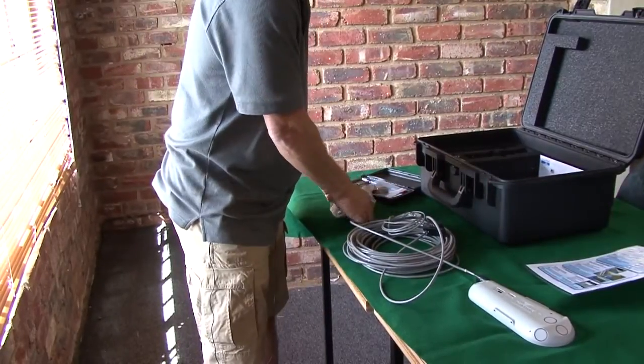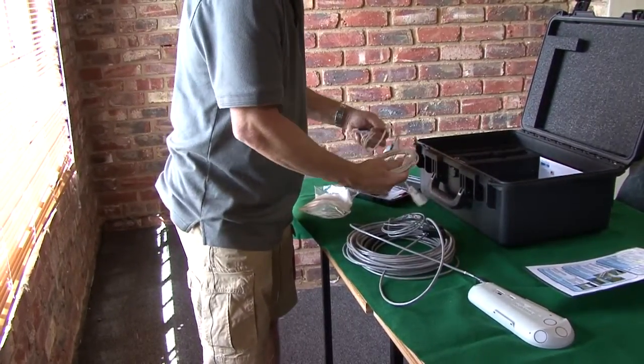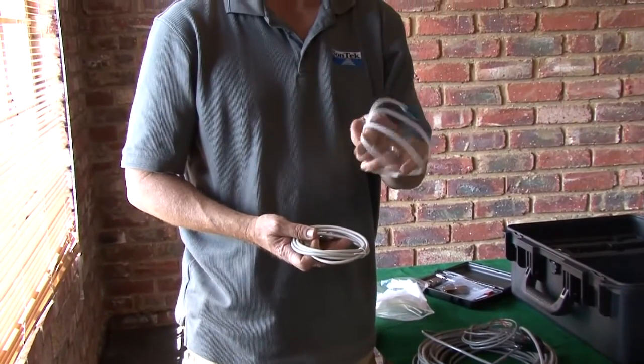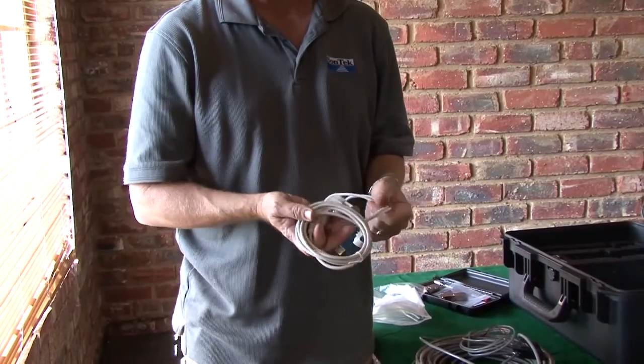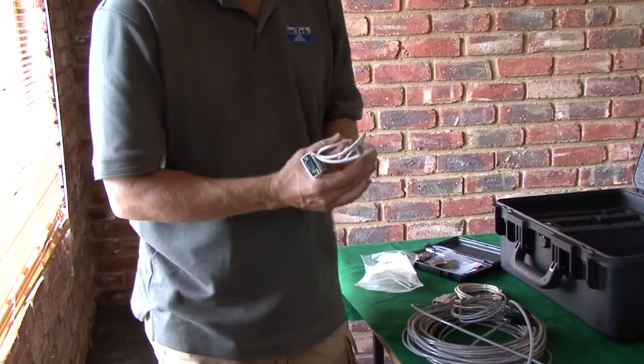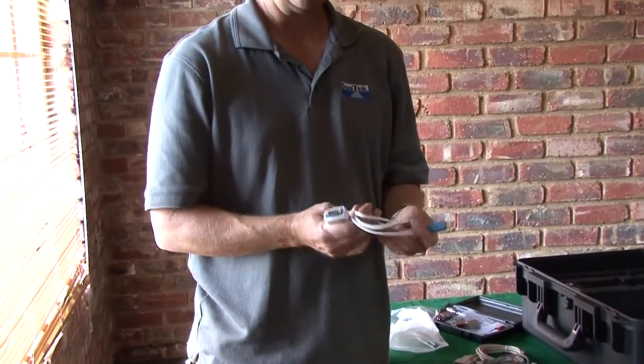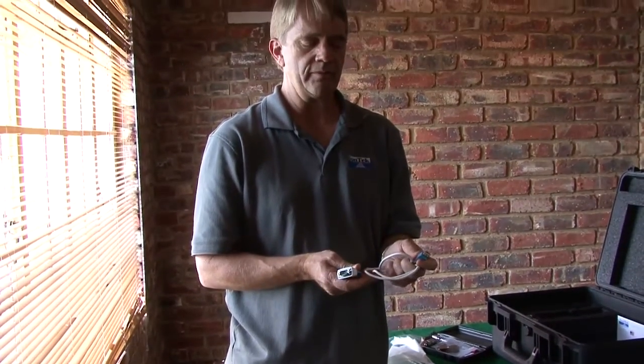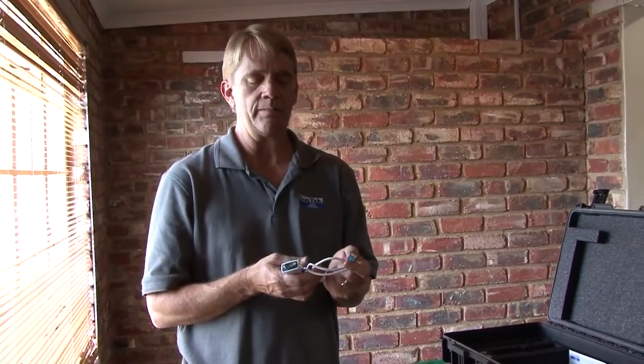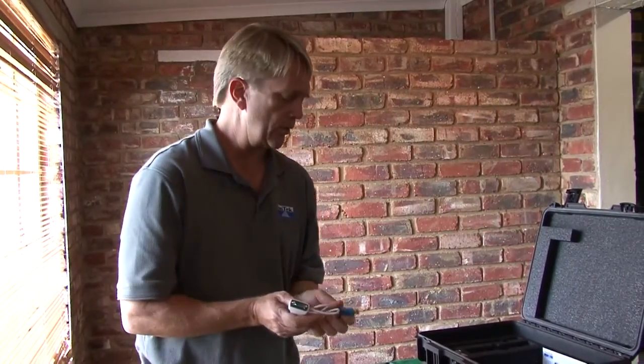To actually talk to the device with our computer, your IQ should come with an RS-232 connector and an RS-232 cable. We always like to connect our computers using this RS-232 USB converter. Number one, it makes the communication much more reliable. Comports on laptops tend to vary in quality, so we've provided one of these to minimize the complexities or problems that may arise with the comports.